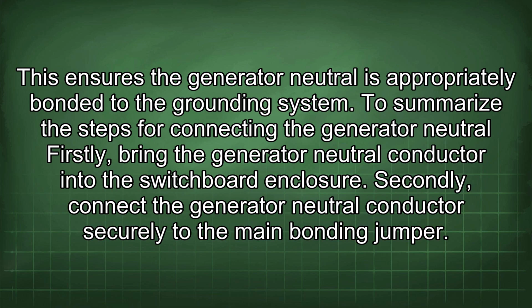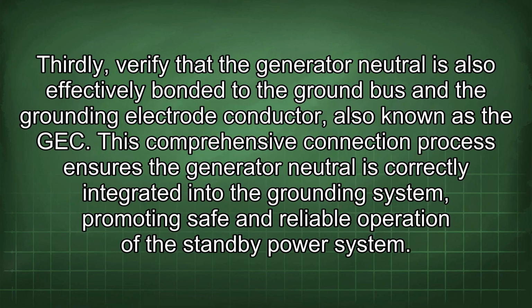To summarize the steps for connecting the generator neutral: firstly, bring the generator neutral conductor into the switchboard enclosure. Secondly, connect the generator neutral conductor securely to the main bonding jumper. Thirdly, verify that the generator neutral is also effectively bonded to the ground bus and the grounding electrode conductor, also known as the GEC. This comprehensive connection process ensures the generator neutral is correctly integrated into the grounding system, promoting safe and reliable operation of the standby power system.